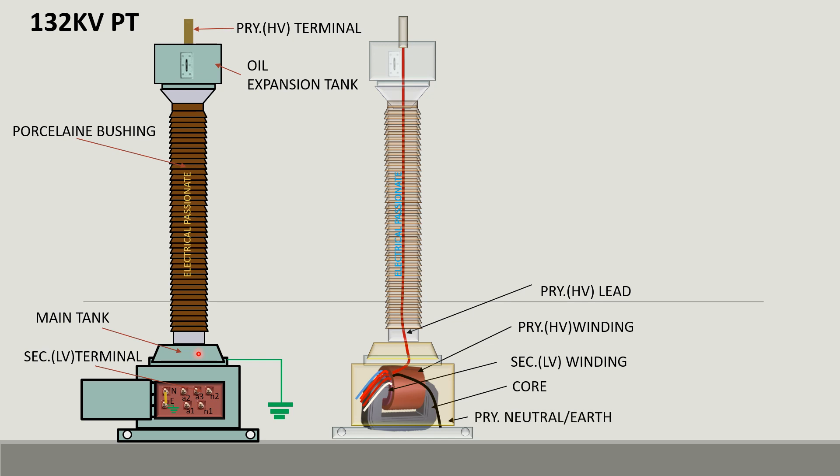One end of the primary lead of the HV side connected with HV terminal is also insulated. Another end of primary lead is connected with HV winding of the potential transformer, and other end of the HV winding is connected with body for earthing through solid link.